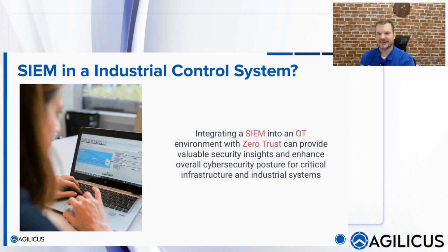We typically go with what's called a SIEM. Now, this has been used for a number of years in the IT space, but more and more it's being connected into the OT space. So SIEM is the security information and event management. Think of it as a logging repository where every single device that has to do with security, access logging, syslogs, firewall, intrusion prevention systems, for example, something on your DMZ of your OT network feeds its logs into a SIEM. The role of the SIEM is to host it, to correlate it, but also allow you to do something called threat hunting. Look in real time as to who's doing what across all systems and link it all together into a single pane of glass.